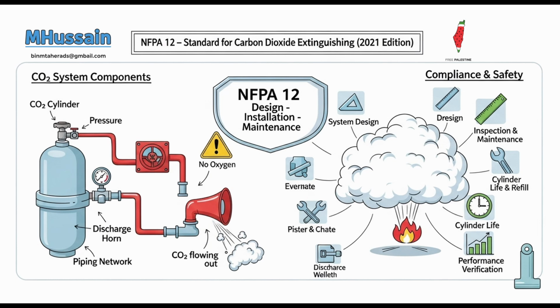Secondly, carbon dioxide provides its own pressure for discharge. Self-pressurizing. Which simplifies system design because you don't need separate pumps or complex pressurization systems, which means fewer points of failure and easier installation. Makes sense. Because it's a gas, it can penetrate and spread efficiently to all parts of an enclosed hazard, reaching nooks and crannies that other agents might miss. Gets everywhere. And, as you mentioned, its electrically non-conductive nature makes it perfectly safe for use on energized electrical hazards. Critical for power facilities. Which is a major advantage in places like power substations or high-voltage switchgear rooms, where maintaining power is crucial or where water could pose electrocution risks.